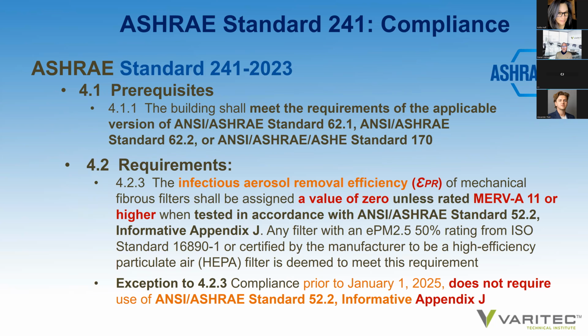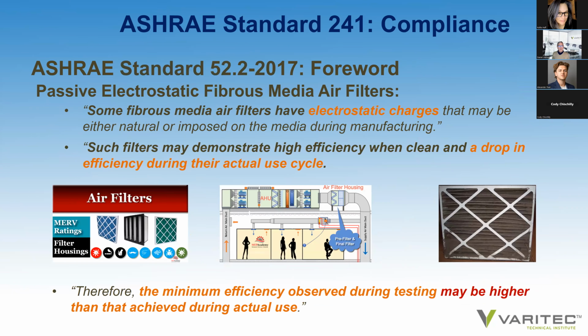Well, under the prerequisites, again, the standard says that every building must provide the ventilation rates prescribed by 62.1, as well as Standard 170 for healthcare applications. It goes on to say, and this is what's surprising, that the infectious aerosol removal efficiency, a term we're going to visit later on as well, of mechanical fibrous filters shall be assigned a value of 0 unless rated MERV A11 or higher when tested in conformance with ASHRAE Standard 52.2 Informative Appendix J. So I went to Standard 52.2 Informative Appendix J and found something rather interesting.